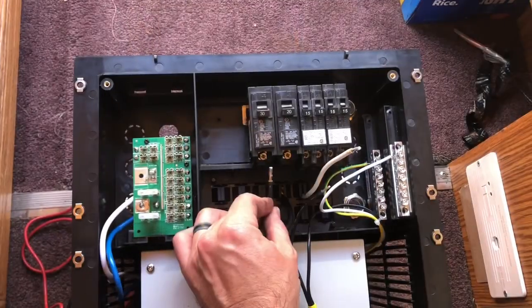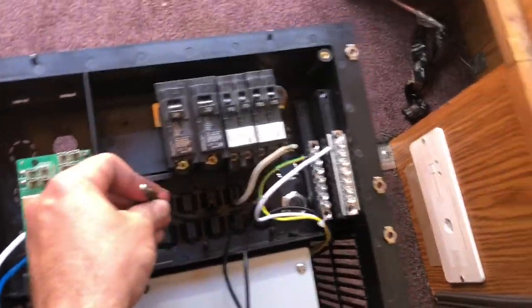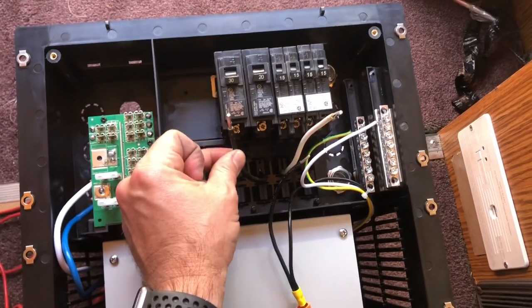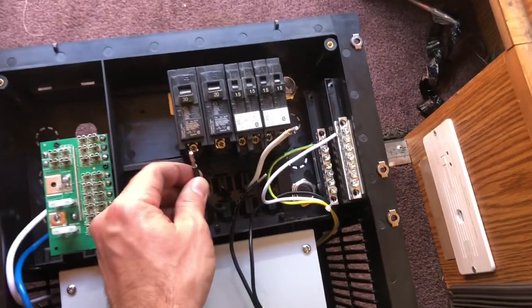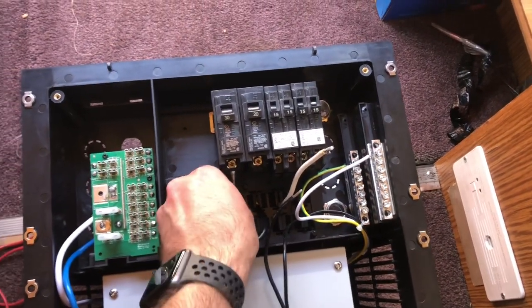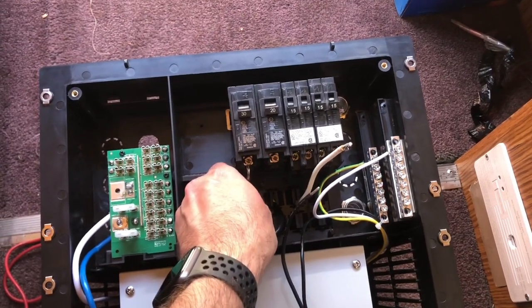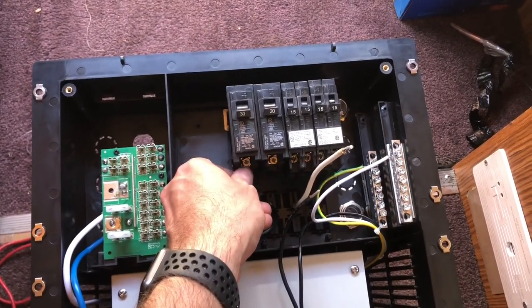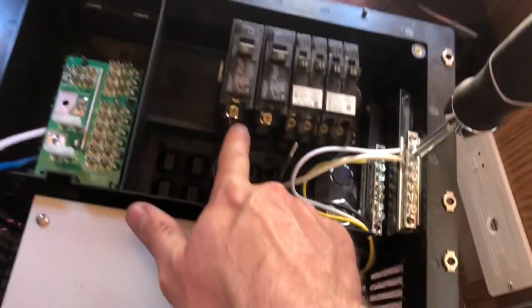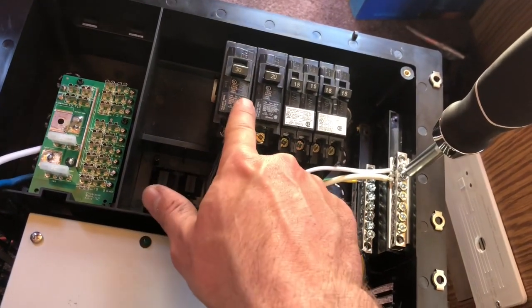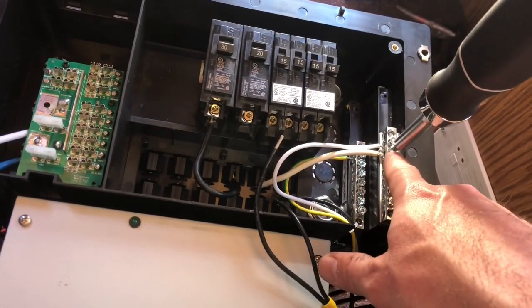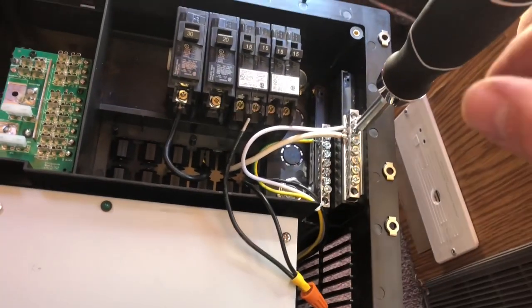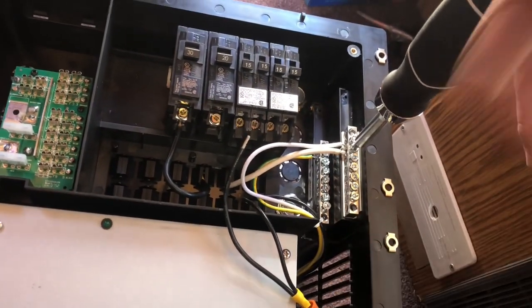Okay, so we're going to start wiring it up. The tag didn't go through, but this is the 30 amp power. I got the tag on the back side so I know that's the 30 amp. We're going to wire that into the circuit breaker and tighten it down with the square bit. We'll take the positive side to the 30 amp breaker, and the neutral side to the bus bar. Make sure those are good and clamped down with good torque.